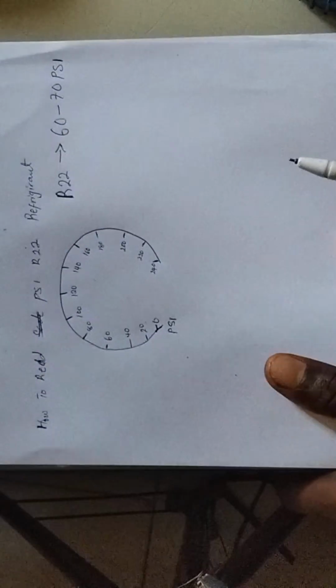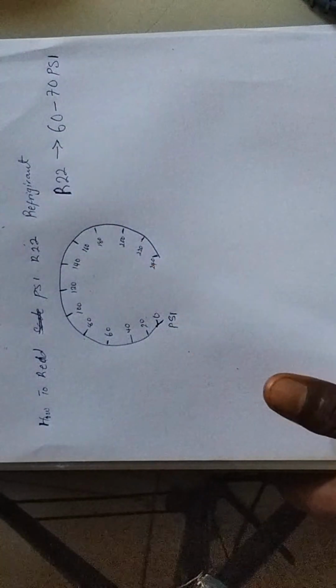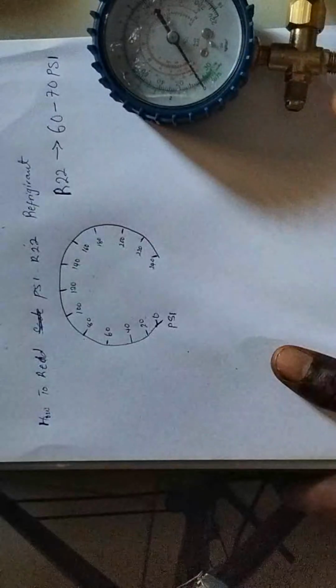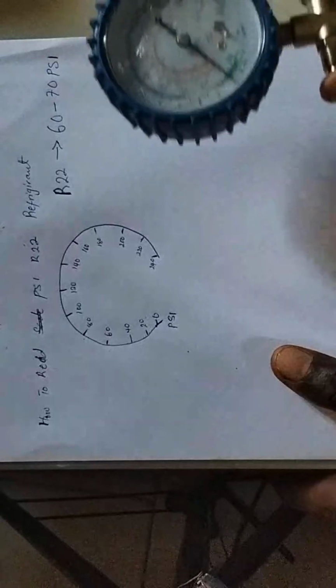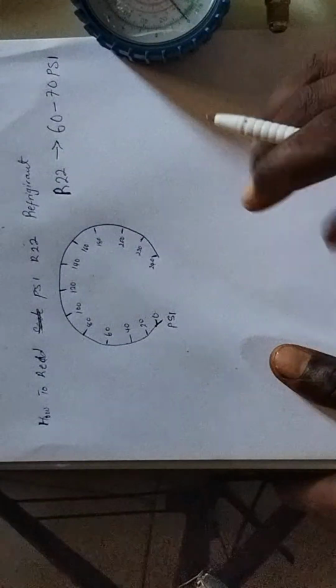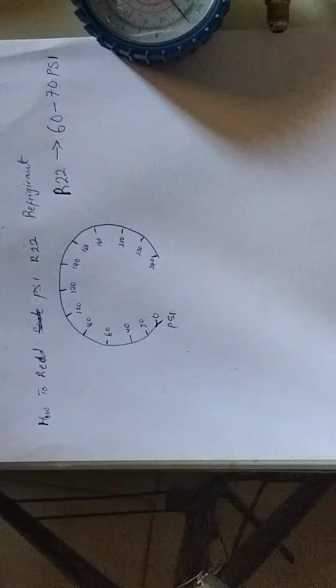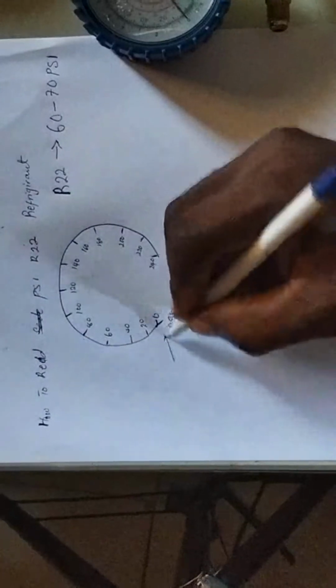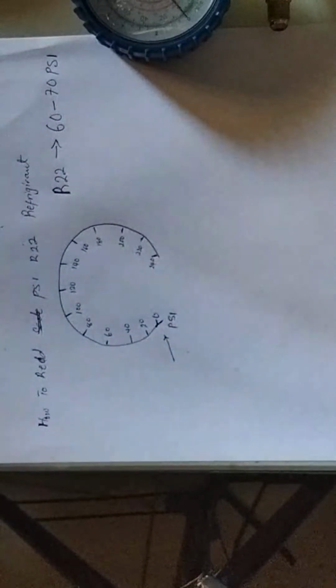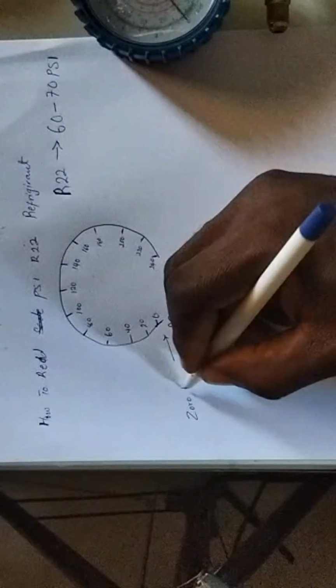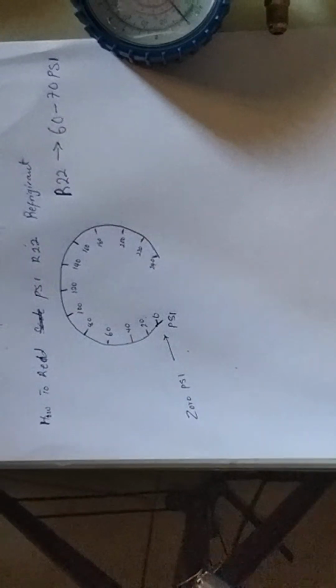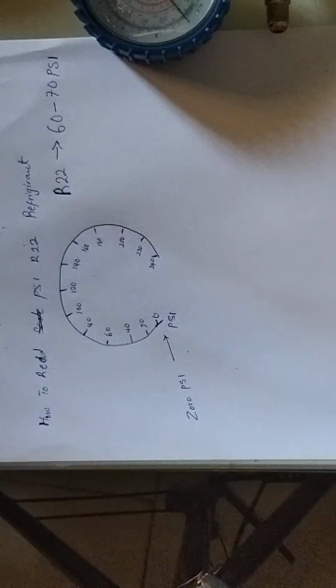So this psi means pounds per square inch. I believe you should know that before now. So we are now dealing with R22 scaling here. When you set up your gauge on your air conditioner, if you don't have any refrigerant on the system already, what you notice on the scale is 0 psi. It will start from 0 psi. That is what you notice when charging a fresh system that doesn't have a refrigerant on it.